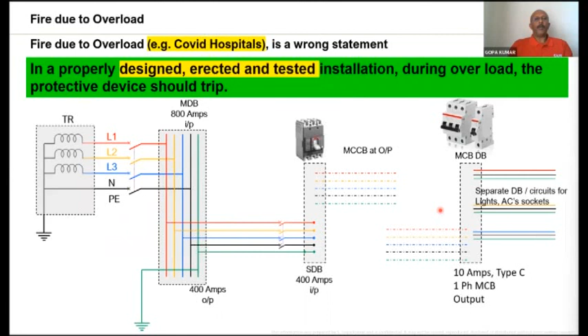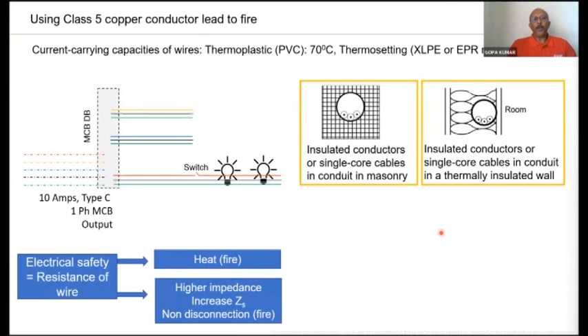Now, across India, one of the culprits creating fire is the copper wire. Copper wire manufacturers always come with the words electrical safety. They use the words electrical safety as a marketing tool. They always say that I have FR cable, FRLS cable, low smoke cable, and so many technical things. Actually, these are related to the insulation of the wire. What is important for electrical safety is how much heat is produced in the wire. Several calculations are applicable here.